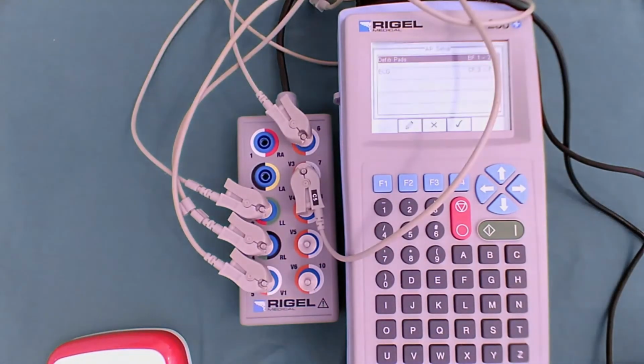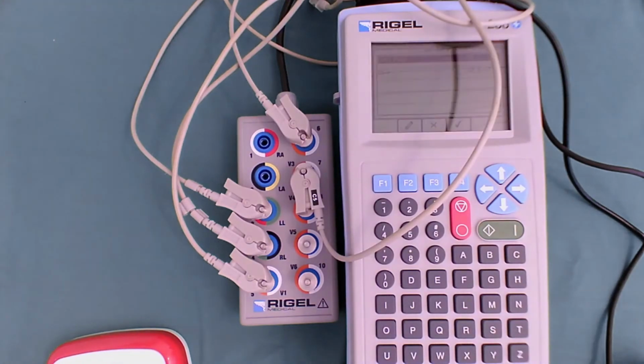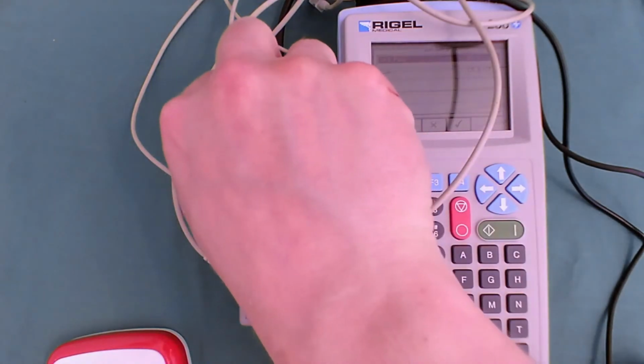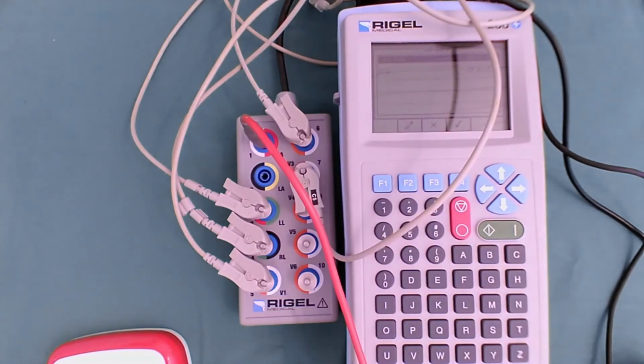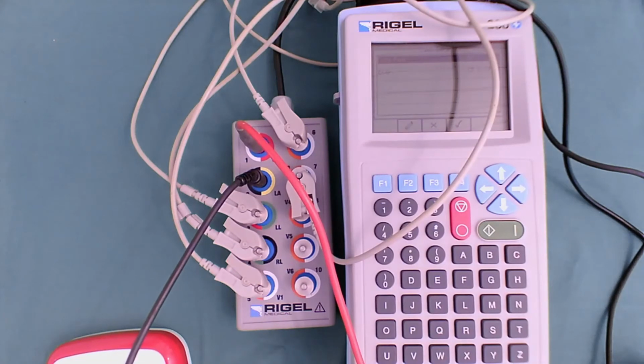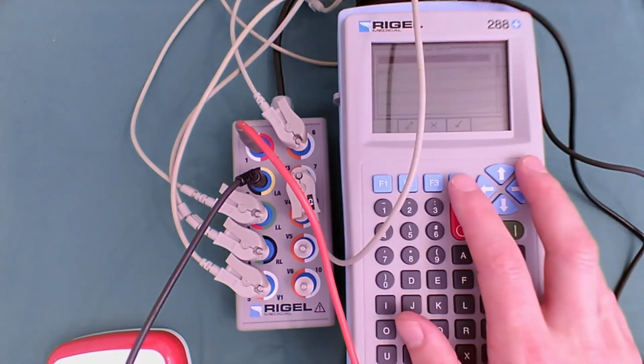As it's an electrical safety test, it's not important where these are configured, and there's no ECG simulation. It's just for electrical safety. So all 5 go on 3 to 7. And then RA and LA is telling us on here 1 to 2. And you can see the numbers just down the left hand side. It's for our defib pads. And now that's already configured for your automatic test.